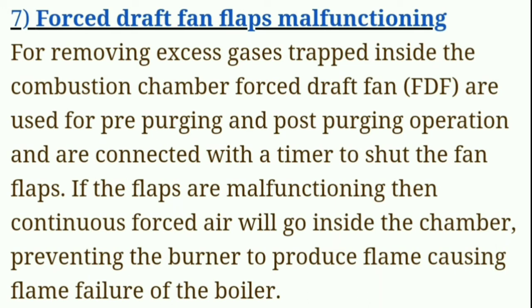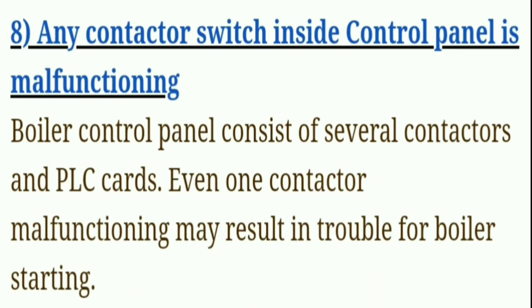Seventh, the forced draft fan flaps are malfunctioning. For removing excess gases trapped inside the combustion chamber, forced draft fans (FDF) are used for pre-purging and post-purging operations and are connected with a timer to shut the fan flaps. If the flaps are malfunctioning, continuous forced air will go inside the chamber, preventing the burner from producing a flame, causing flame failure of the boiler.